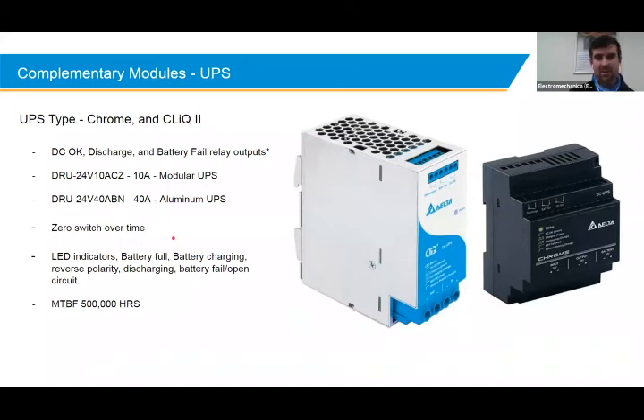They enjoy a 0 switchover time. So from mains failure to battery, it's instant. You've got LED indicators on the unit for battery fail, battery charging, reverse polarity, discharging, battery open circuit, etc., as well as 3 relay contacts for discharge, battery fail, and DC OK as well. So these are nice. You can tie it back into the PLC, and the PLC will know that power is down and we're running off battery power. It can send alarms back to the controller, for instance.